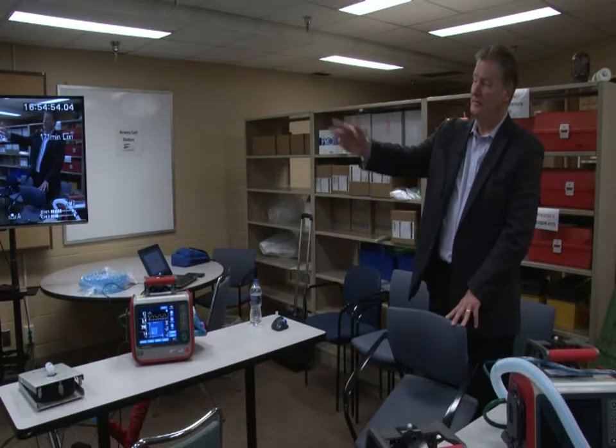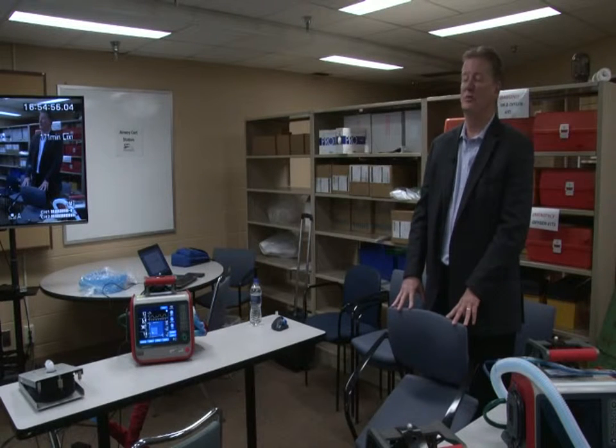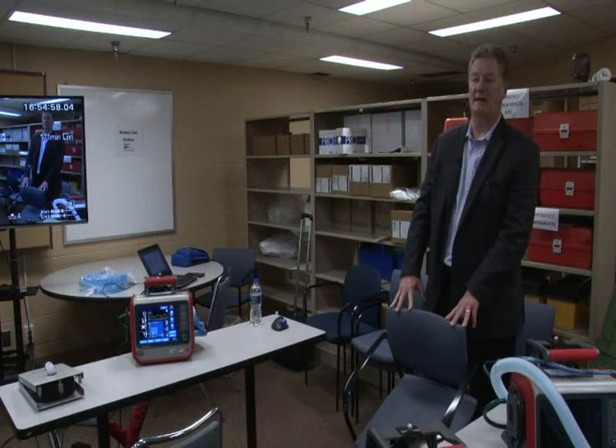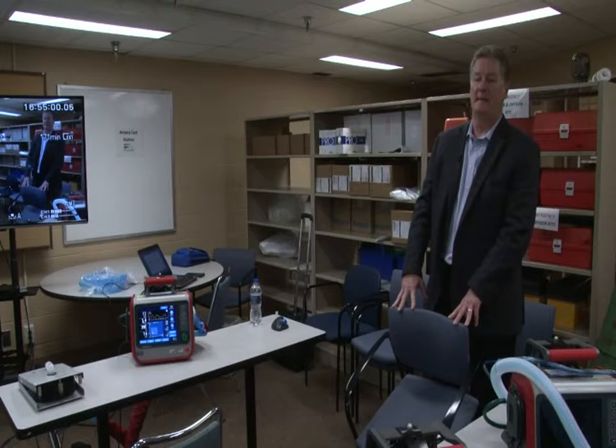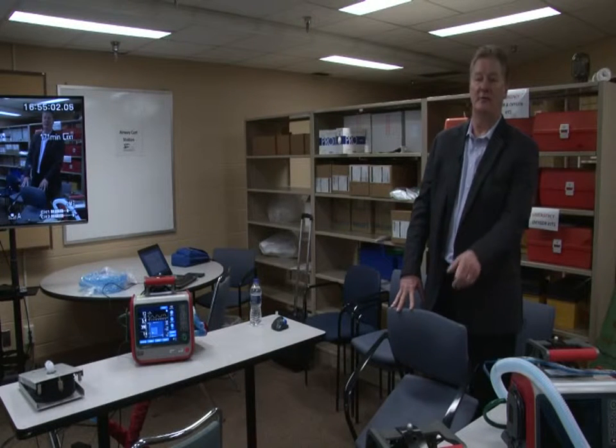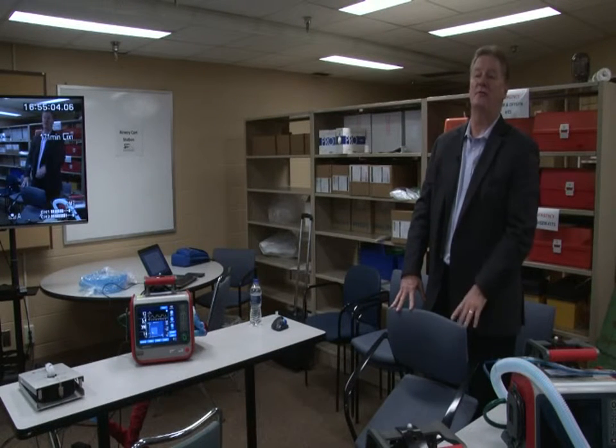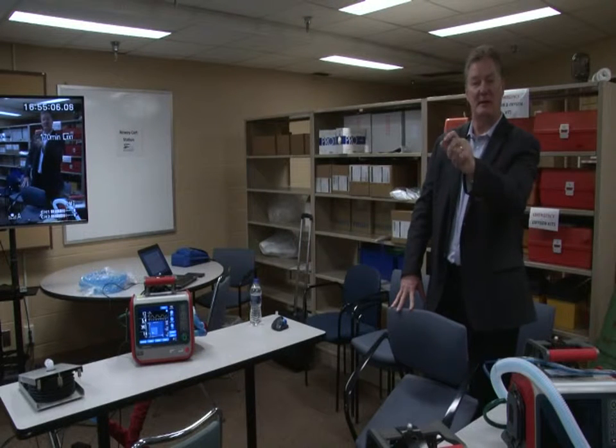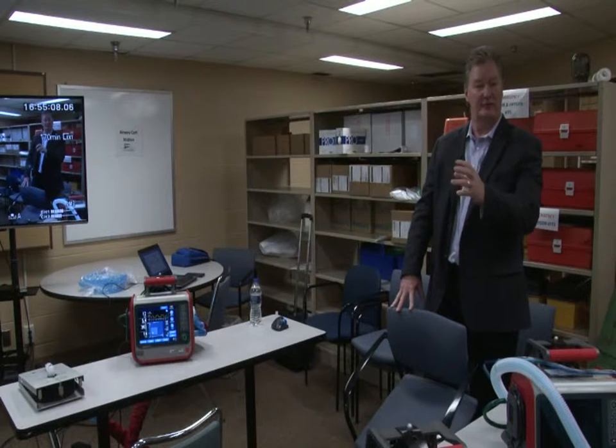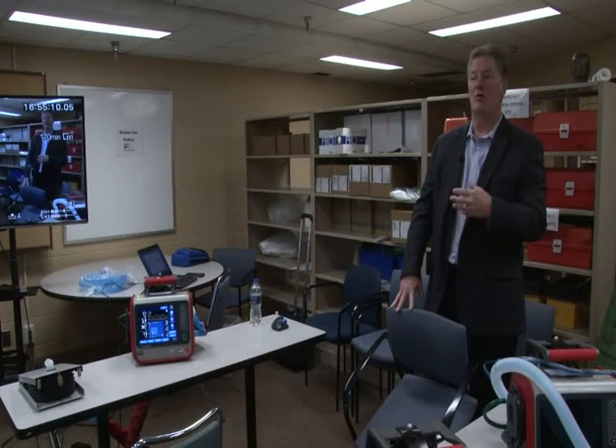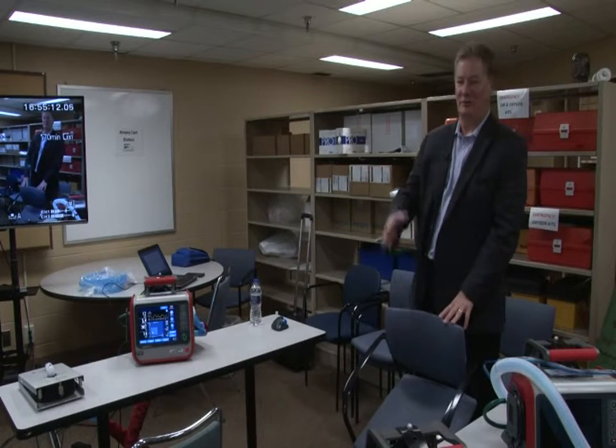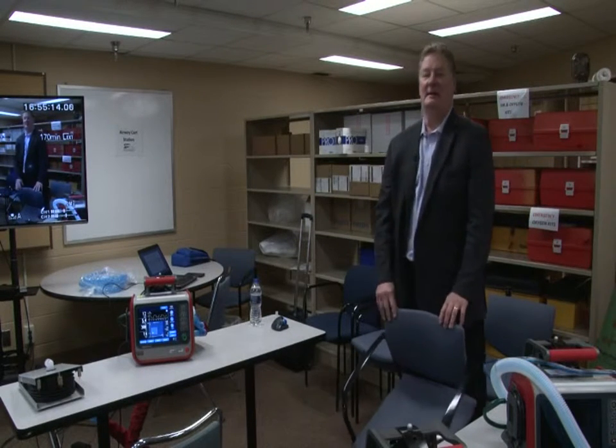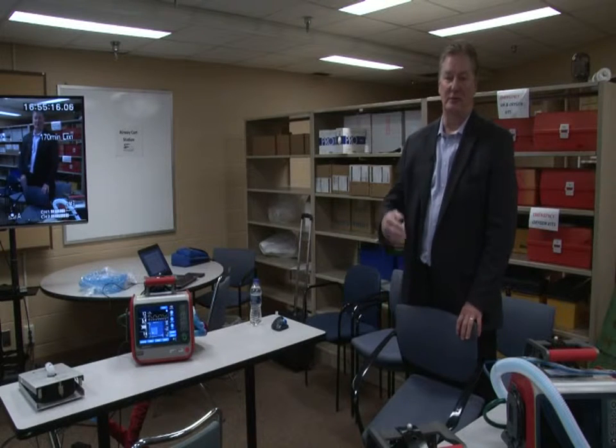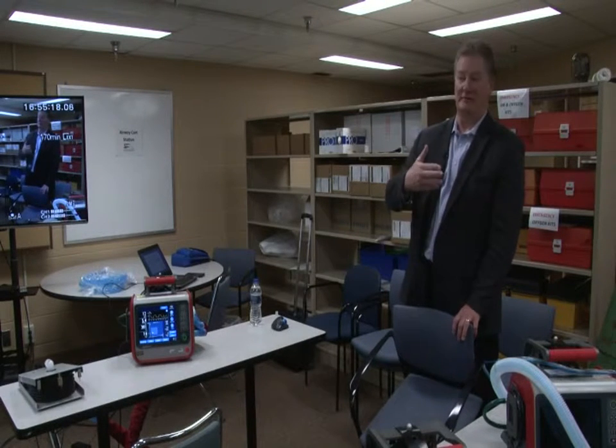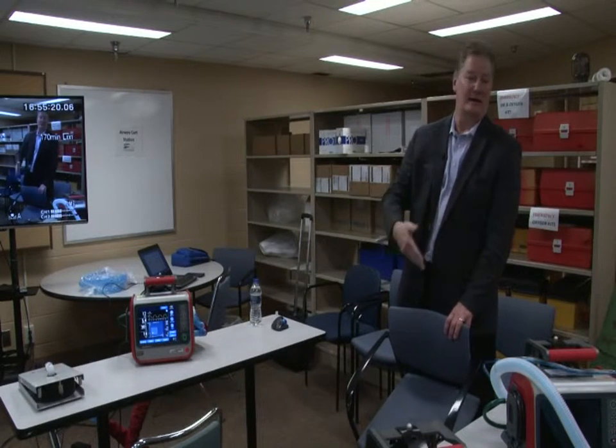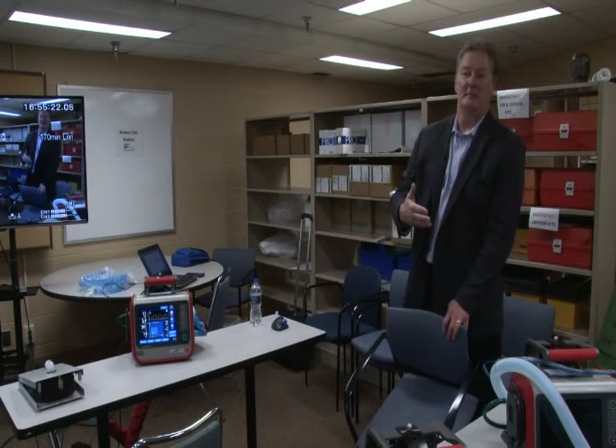And that's accomplished through something called volume targeted pressure control, so you get the best of both worlds. You get a constant volume and a square pressure waveform that's constantly being adjusted by the ventilator in pursuit of a target tidal volume. So it's more physiologic because nobody breathes the same tidal volume every time. And typically volume control ventilators used a fixed flow, so it was X amount of volume at X rate at X amount of flow rate. But nobody breathes like that.